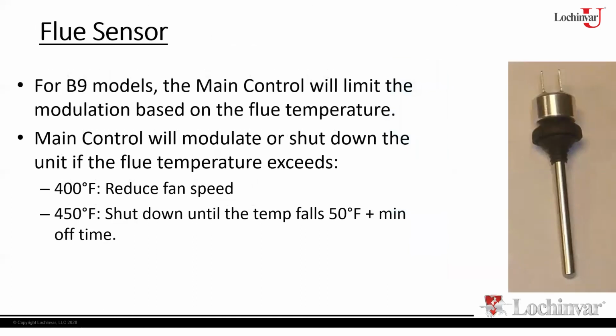All right. Then we've got a flue sensor. Now, it's a category 4 appliance. I'm venting it with stainless steel. I don't necessarily need to monitor the temperature in regards to protecting PVC vent, right? I'm not venting it with PVC or CPVC or plastic, so I don't need to protect it from that aspect. So I've got a flue sensor here, but what's it really for? Well, primarily it's going to be used on the B9 model.